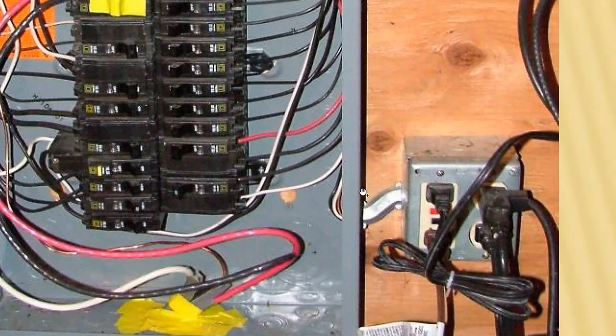So let's say if there was no bonding wire connected to the box, then the box would be just floating in the air, so to speak, electrically. Now, there is going to be a neutral wire connected to one of the terminals of the receptacle, and a hot wire connected to the other terminal, and everybody happy, right? Okay. What happens if, by some sort of accident, that hot wire becomes detached and it touches the metal box? Well, that metal box becomes hot, which means if your feet are grounded, and usually they would be, and you touched that metal box, you would be providing a current pathway from the box through your body to ground.